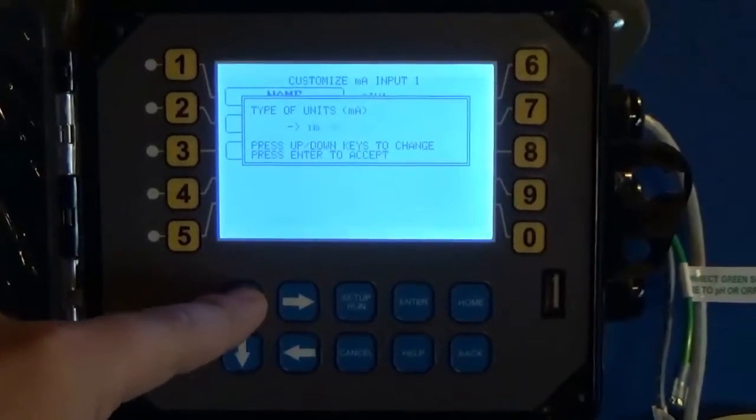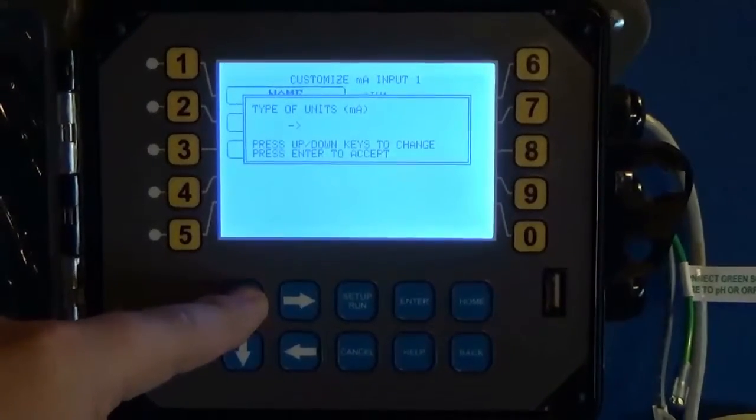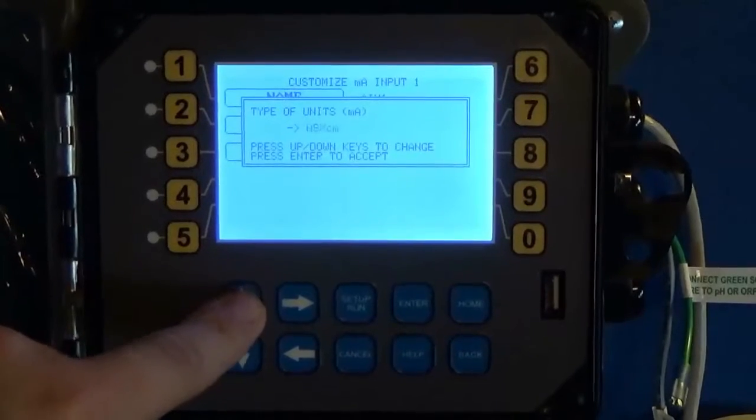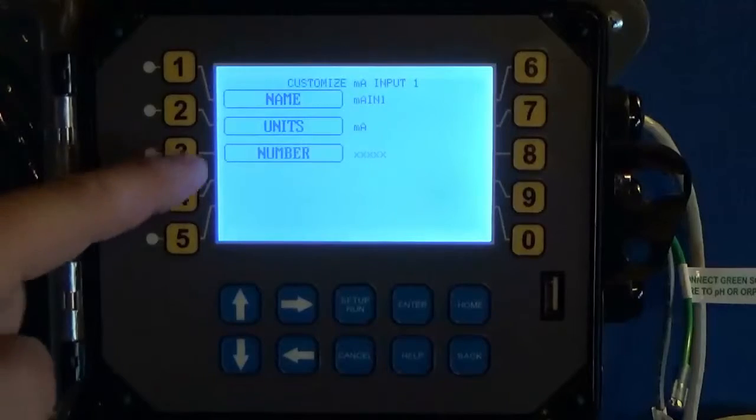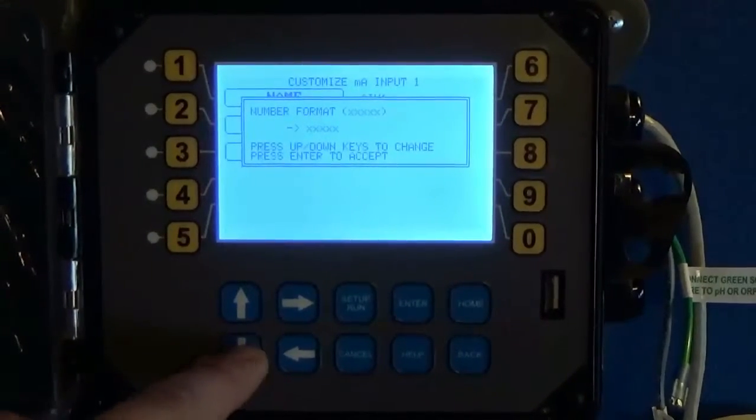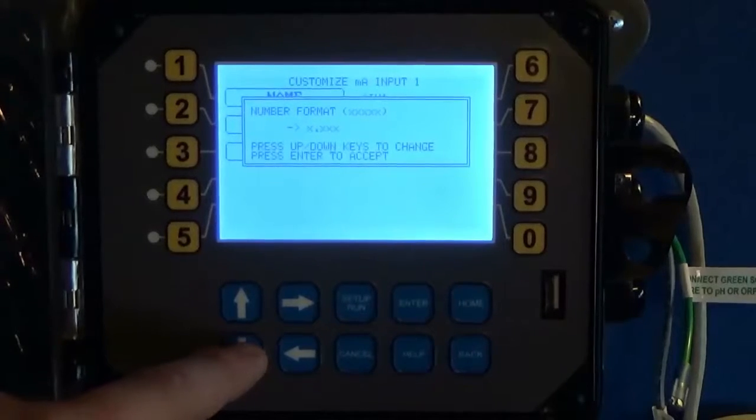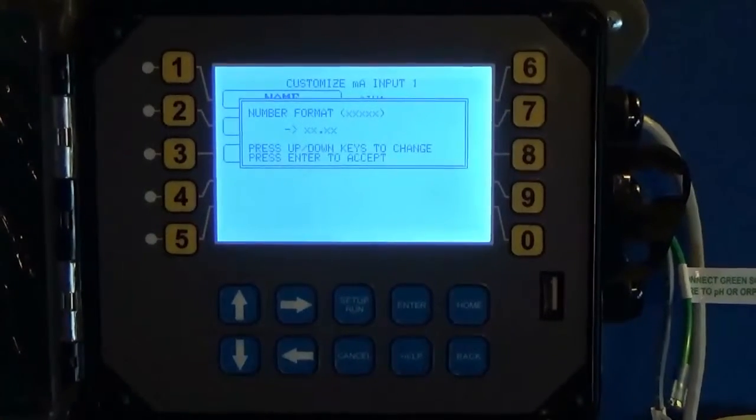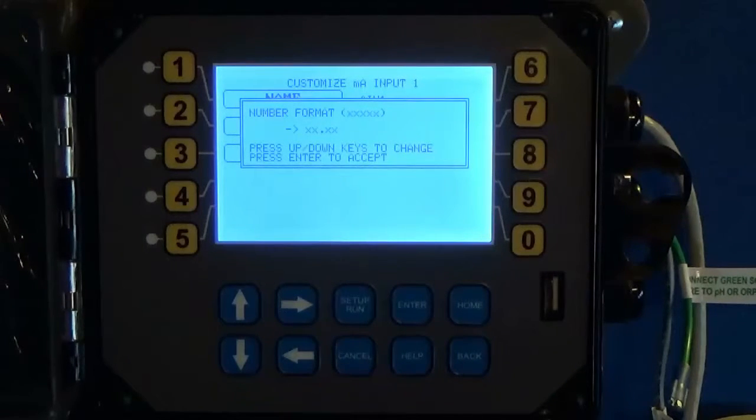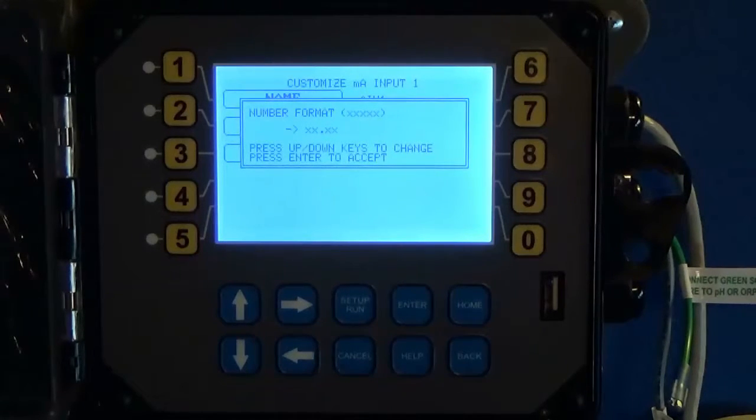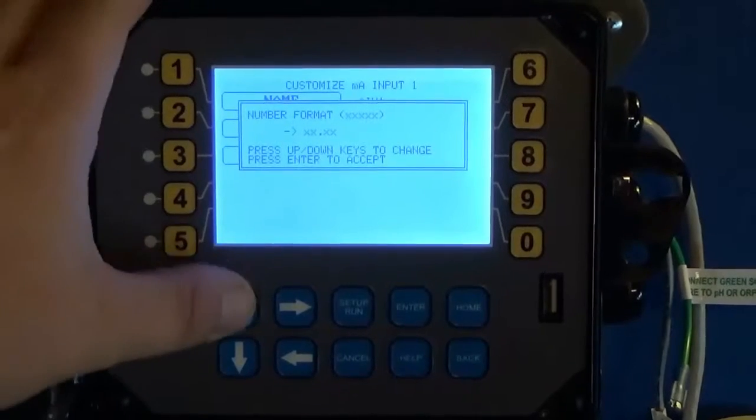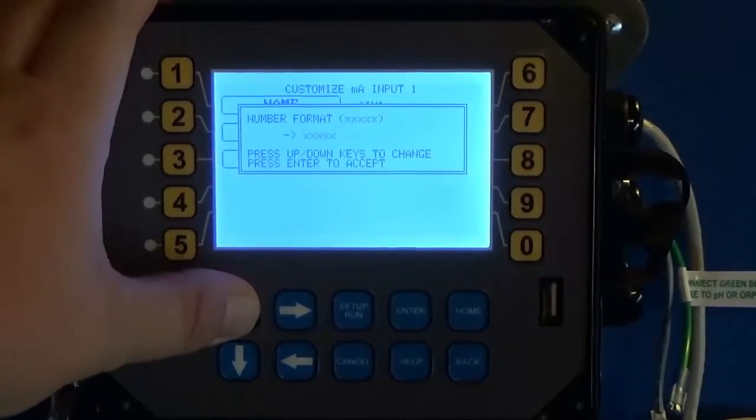If you're looking at milliamps you can give it a number value. Do I want whole numbers? Do I want a whole number and three decimals? This is a lot of times based on what you're bringing into the unit. Whatever sensor you're using will usually provide you with the range that it's good at and the measurements, so you would refer to your product manual of whatever you're connecting to know what that proper number format is.